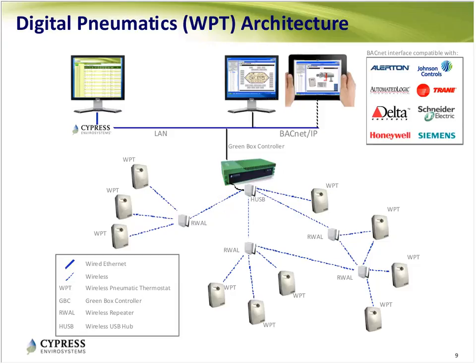Basically, if you look at the green box controller, one green box controller typically can handle up to 225 thermostats. So if you have more than that, a big high-rise building with 1,000 thermostats, you just put more green box controllers, typically one for every 3 to 4 floors. Now, the thermostats talk wirelessly with the green box controller, and if the distance is too far, we have a repeater. Normally, one repeater would serve up to about 10 thermostats, and we'd have up to 225 thermostats per green box, and up to 10 to 15 thermostats per repeater.